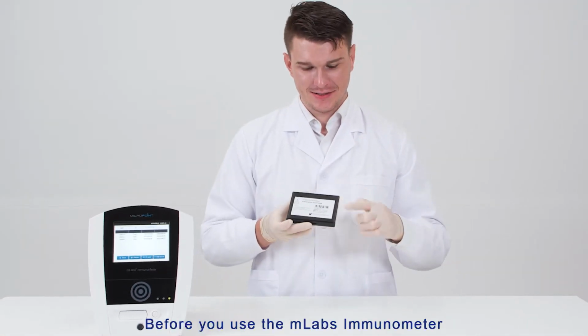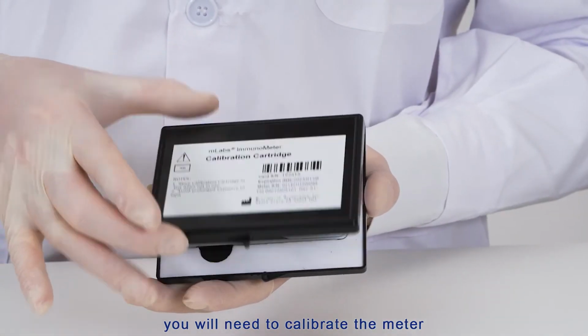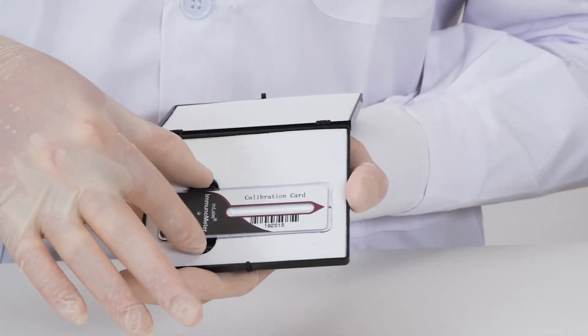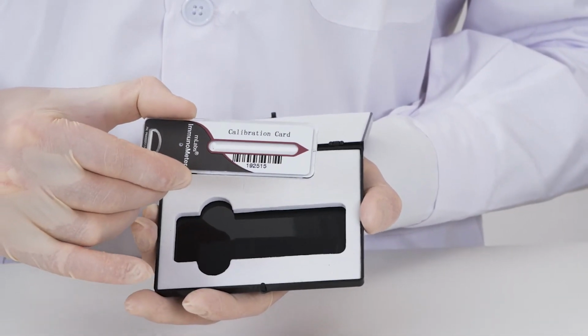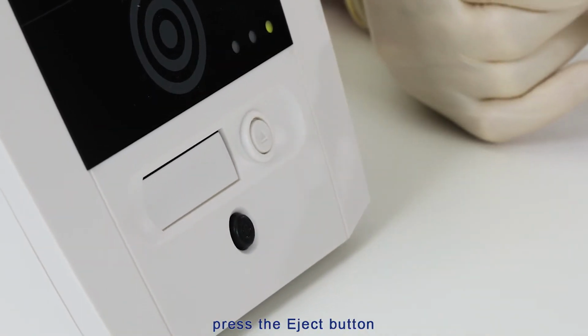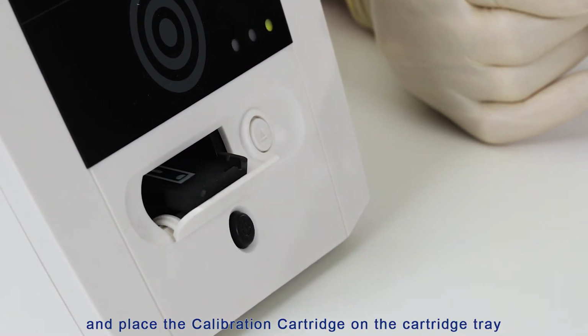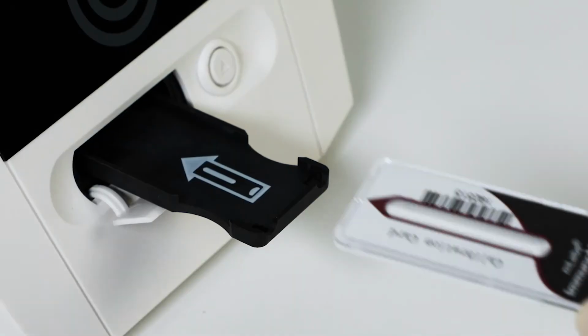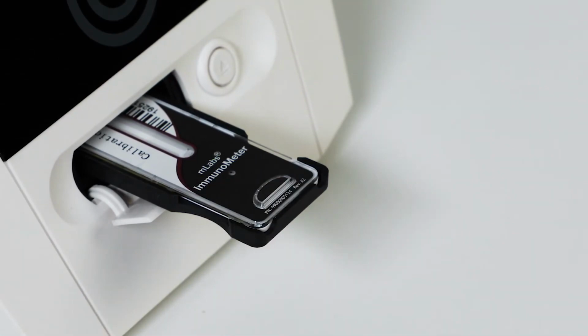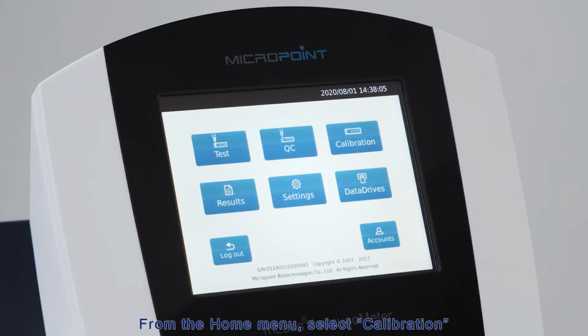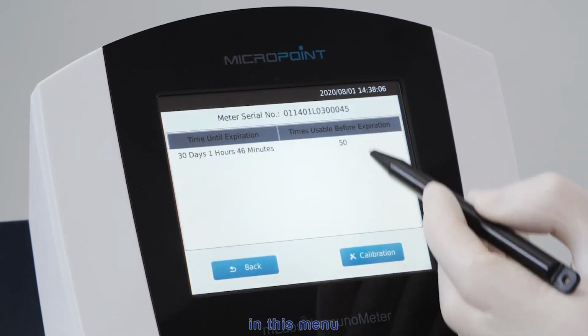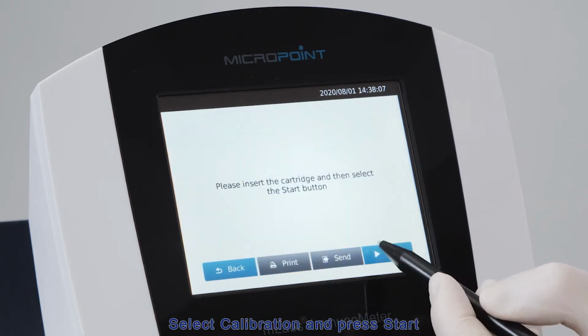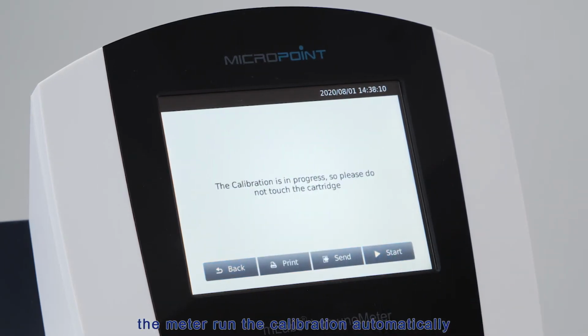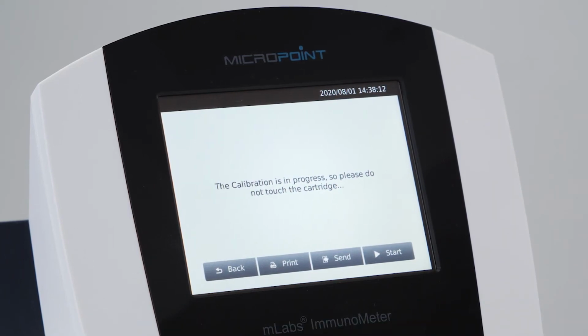Before you use the mLabs Immunometer, you will need to calibrate the meter. To perform a calibration, press the Eject button and place the calibration cartridge on the cartridge tray. From the Home menu, select Calibration. In this menu, you can check expiration date for calibration and usable times before expiration. Select Calibration and press Start. The meter runs the calibration automatically.